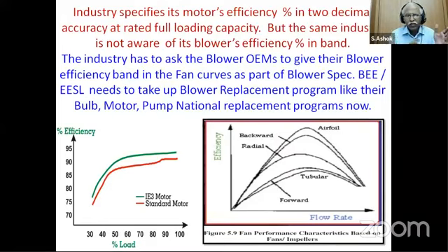So you can see the flat efficiency curve of the motor and the inverse umbrella type efficiency of the airfoil or the backward curved. Everything is a narrow band, whereas the motor is a broad band. If the efficiency of the motor and this impeller are superimposed, this is the best efficiency possible for the given impeller. So for an air conditioning segment, definitely the airfoil impeller is the best suitable impeller. It can be a centrifugal backward curved inclined, or a plenum type, or a plug type also.